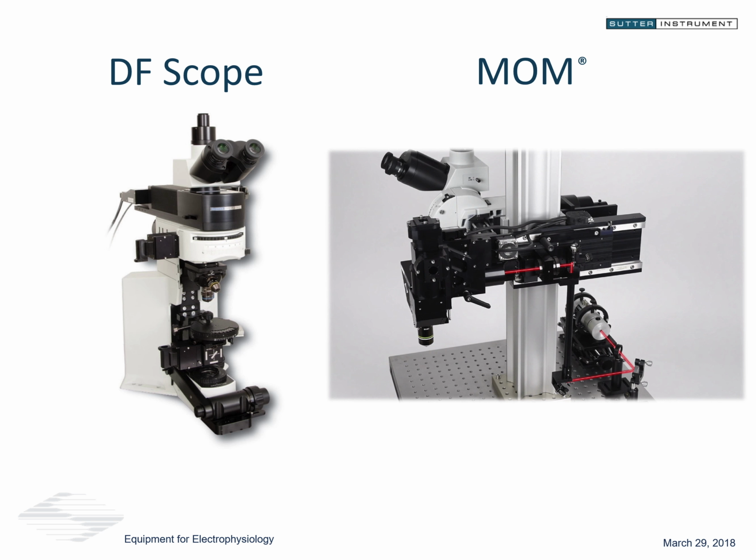There are certain things that we can consider about each of the two-photon systems. For example, there are various scanner options. We have resonant scanners, galvo scanners, 3mm galvos, 6mm galvos, all for tuning the microscope for the appropriate application. You could say the same about the detector paths. We have 2-channel detector paths, 4-channel detector paths, short paths, wide 2-inch collection optics, for example, all with various trade-offs.